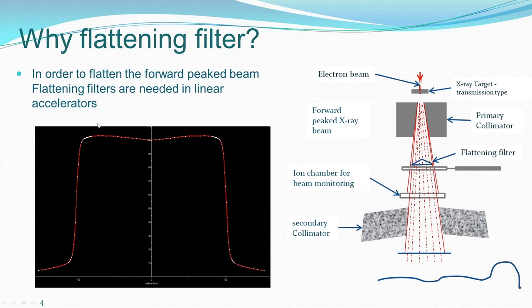The final resultant beam profile became a flat beam profile. You could note it is not strictly flat — there is a dip at the middle, meaning the central axis dose is lower than the off-axis dose. This we refer to as the horns. The reason is that one flattening filter is designed for a particular energy and reference field size; when you go to other field sizes, it may not be exactly flat.